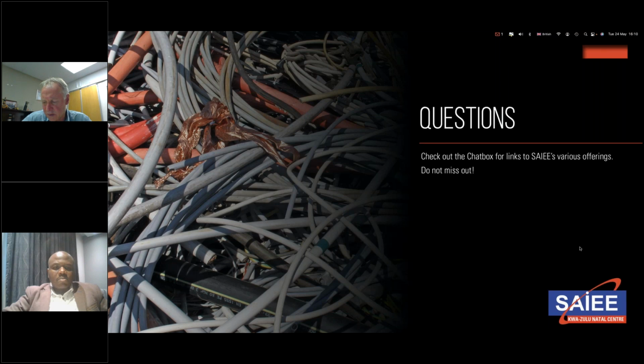There would be the concern, particularly if you consider, say, XLPE, which has an expansion coefficient about 10 times that of copper. If it expands and there's a restriction over that insulation in the form of copper wires or tapes or armoring, then you run the risk of pressing into the insulation, and over time with load cycling, even damaging the insulation. So just changing the conductor from copper to copper-clad aluminium or copper to aluminium doesn't really affect the bending radius of the cable.